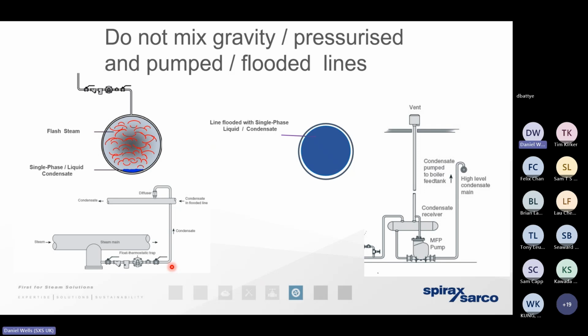One of the benefits is that if we vent that flash steam expansion away, the condensate is reverted to a single phase non-compressible fluid, and we can bring the condensate infrastructure back, maybe thousands of meters, in a much, much smaller pipe size. What we don't want to do is see pumped condensate lines and pressurized condensate lines coming together, because at that point we don't know the extent of the mix of mass, pressures, temperatures, and expansion. And that could create further damage to the infrastructure.